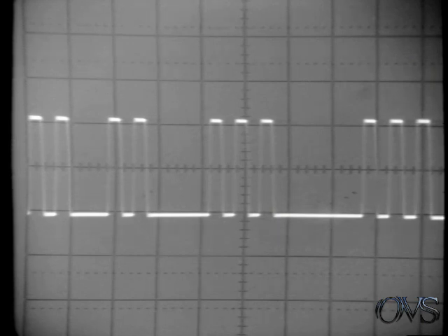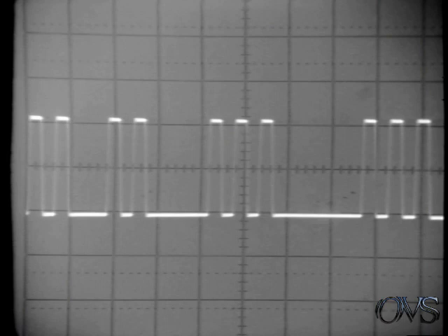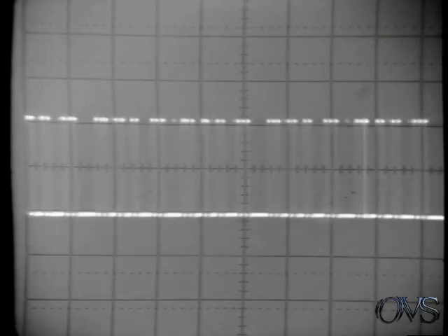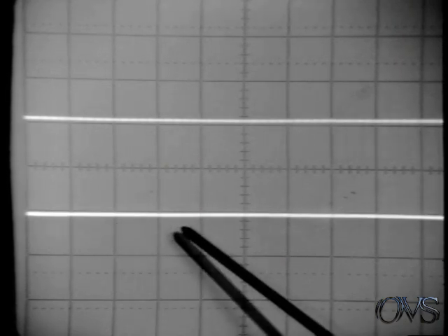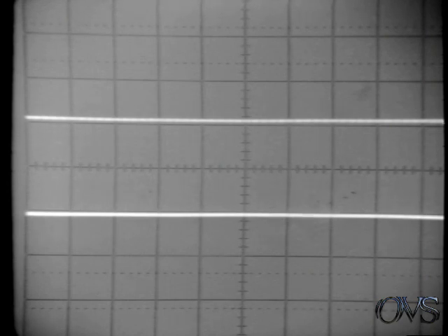Typical applications, because of the lack of trigger signals available, generally require us to view a main sweep that may contain 10 or 100 or 1,000 words. But our measurement requirement asks us to locate and measure only one or a portion of one of those words. By using the delayed time-base generator in conjunction with the delay control, we can do just that.